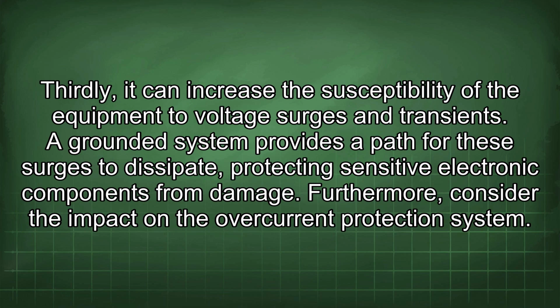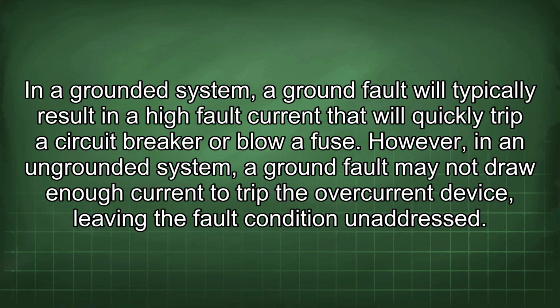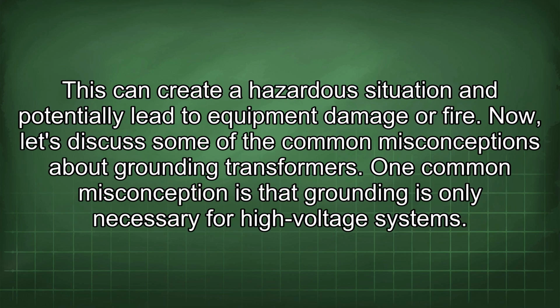Furthermore, consider the impact on the overcurrent protection system. In a grounded system, a ground fault will typically result in a high fault current that will quickly trip a circuit breaker or blow a fuse. However, in an ungrounded system, a ground fault may not draw enough current to trip the overcurrent device, leaving the fault condition unaddressed. This can create a hazardous situation and potentially lead to equipment damage or fire.